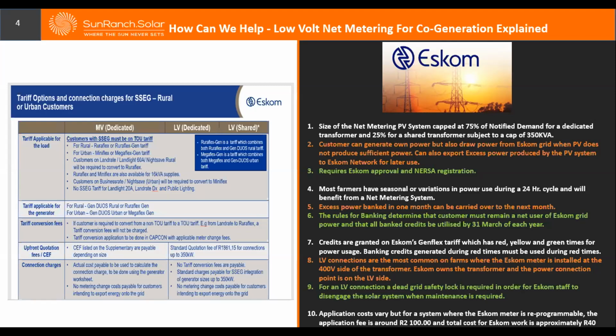So for your LV system, just a couple of requirements for the installation itself: it is a maximum of a 350 kVA solar system. The solar system is benchmarked in terms of 75% of your notified maximum demand, so that is more or less the size of your transformer. So you can go up to a 500 kVA transformer, and you are allowed to install a 350 kVA solar system.